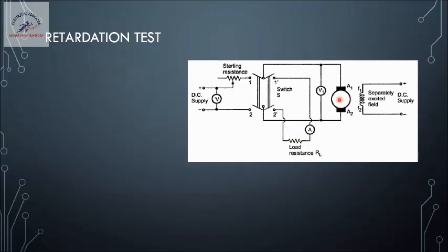So this is electrical braking. In positions 1 and 2, we are not connecting any electrical load to the system. We are not using electrical braking. We are allowing it to come to rest on its own, and we observe the rate of change of speed. To get better accuracy in this test, the beginning of the test is done by running the machine slightly higher than its rated speed.